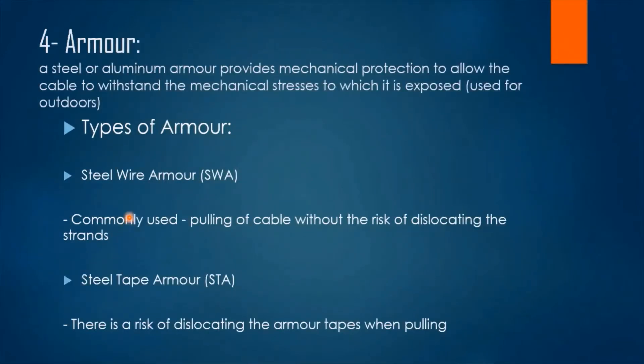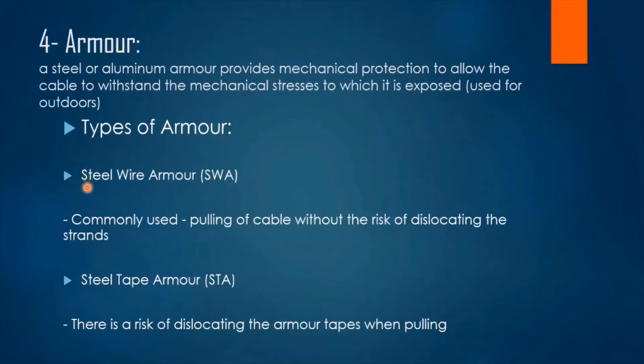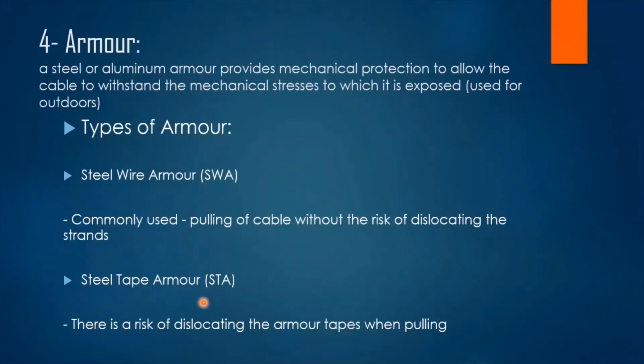The fourth layer is the armor layer — a steel or aluminum armor that provides mechanical protection, allowing the cable to withstand mechanical stresses. We mainly use armored cables for outdoors to prevent mechanical stresses from damaging the cable. There are two widely known types of armor: steel wire armor (SWA) and steel tape armor (STA). Steel wire armor is more preferred because while pulling the cable, there is no risk of dislocating the strands, whereas steel tape armor has a risk of dislocating the armor when pulling.